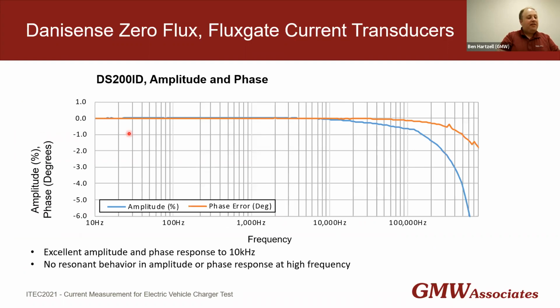Here again, emphasizing the very good amplitude and phase. In addition to being very low, you can also see that it is very level and flat up to about 10,000 Hertz. And even above 10,000 Hertz, there's no resonant behavior in the amplitude or phase response at higher frequencies. So if you need high accuracy measurements, this is just a very, very good choice.